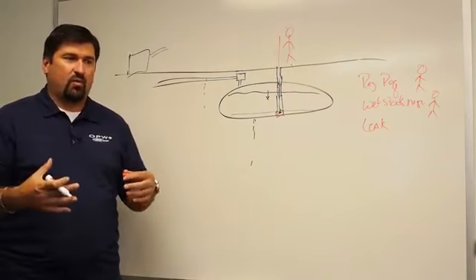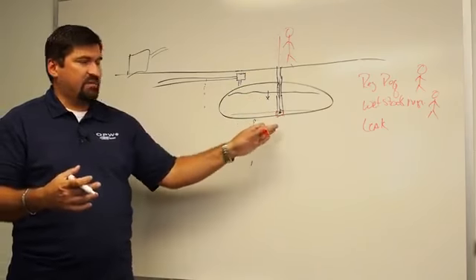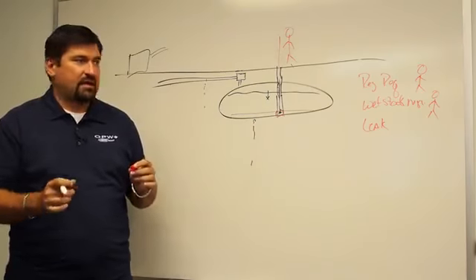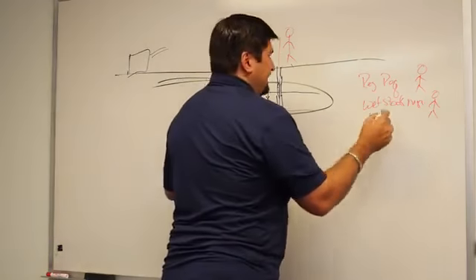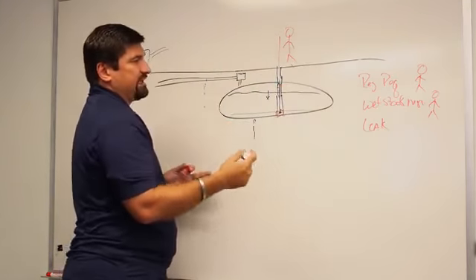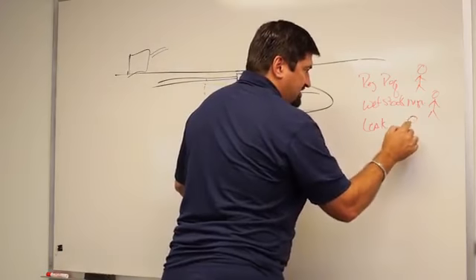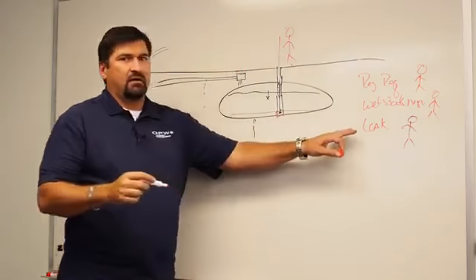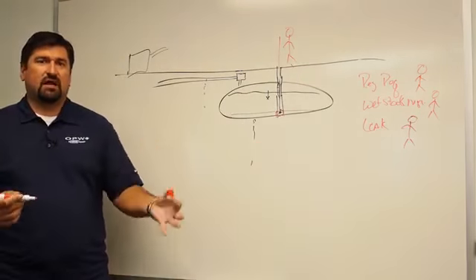So people normally will do an automatic tank gauge to prevent somebody from just constantly banging that stick on the bottom of the tank. The other one is the leak. Since everything is underground, you can't see it, you actually have to hire somebody to come out and test your tanks and your lines to make sure that they're not leaking.